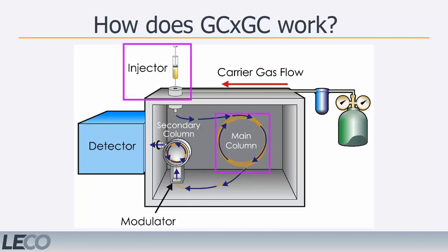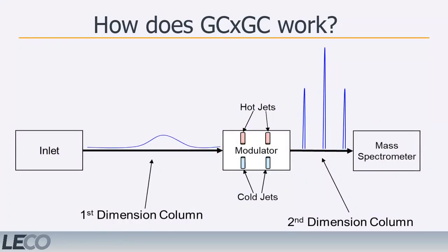The inlet and primary column configuration for a GC×GC system is the same as a standard GC-MS system. Peaks eluting from the primary column are quantitatively segmented into smaller sections by a modulator before being released into the secondary column. This segmenting, combined with the cryofocusing of a thermal modulator, delivers optimum peak widths to the secondary column. The partitioning of the effluent before it passes through the secondary column allows the analytes to be sent in discrete segments without overlapping. The modulator is critical in creating a retention plane of the first dimension separation and allowing second dimension separation to be achieved.